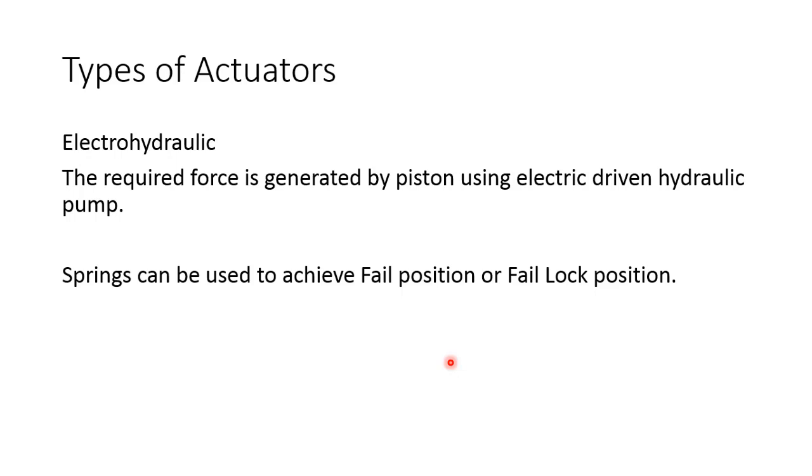Also, if the stroke time is a few seconds, this can be the most suitable choice. Again, this could be either single acting or double acting. Single acting can have one side fail and the other side, one side can be achieved by the force from the hydraulic oil, and the other side can be done by the spring. While on the double acting side, it can be hydraulic oil from both sides to achieve whatever position is required.